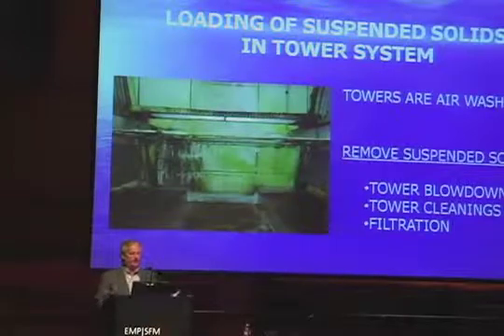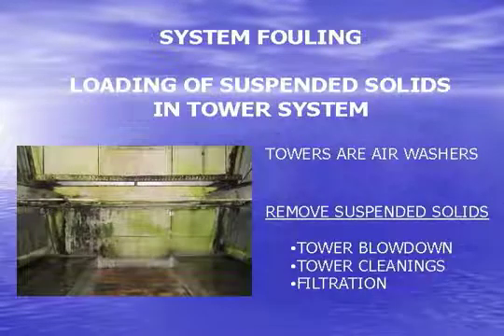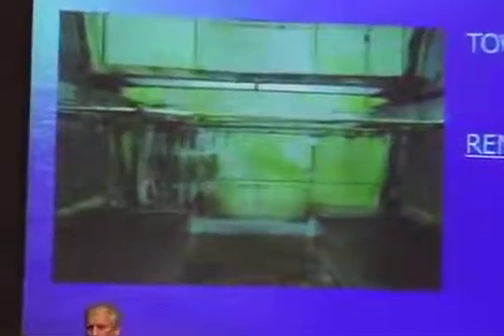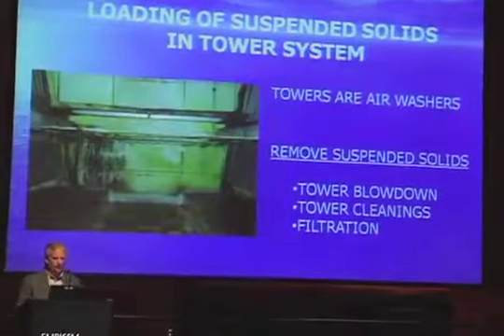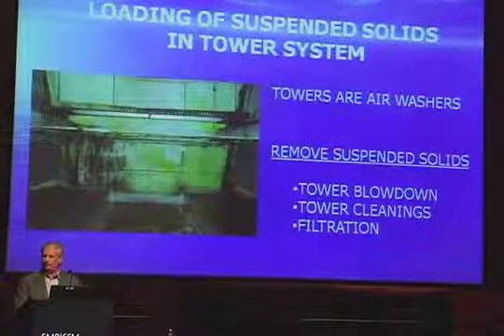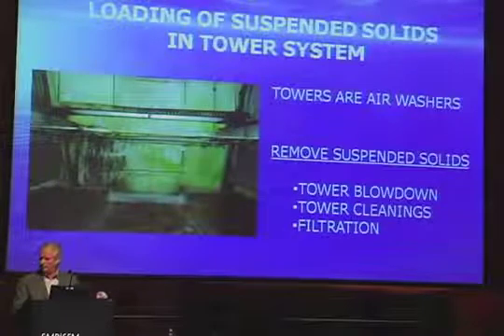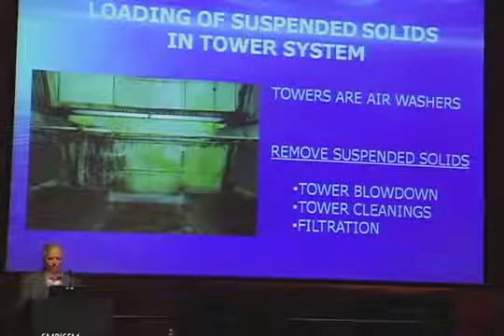The last quadrant we talked about is fouling. If you stand next to a cooling tower, your cooling tower acts as a big air washer. So if you're next to a road, a construction site, or a high-dust area like in Phoenix or Vegas, there are a lot of suspended solids that come into the cooling tower because it actually cleans the air. Unfortunately, the dirt particles go through your system and have a chance to be captured on the pipe surface or heat exchangers, and they also settle in your tower basin. We want to make sure we remove or reduce the amount of particulate matter because it's also a transport mechanism for biological activity — microbes hitchhike and go around the system until they want to settle out somewhere.